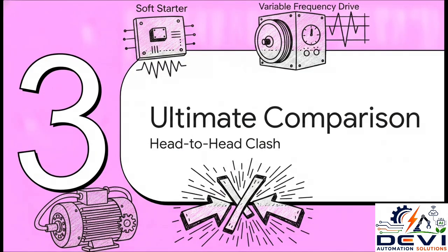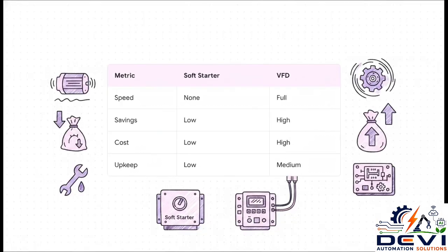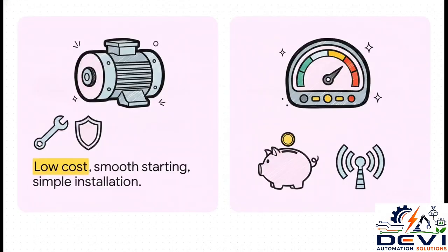Section 3, the ultimate comparison. It's time for the head-to-head clash. When we put them side by side, the contrast is actually pretty stark. Look at speed control. A soft starter offers exactly 0 once it's running, while a VFD gives you full control. Because of that speed control, the VFD has a really high energy saving potential, whereas the soft starter's pretty low in that category. But wait, you have to consider the cost and maintenance. A soft starter is much lower in initial cost and requires very little maintenance. A VFD, on the other hand, is a larger upfront investment and requires medium maintenance just because of its complex electronics.